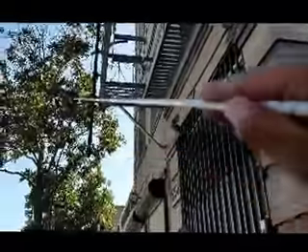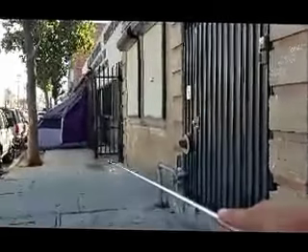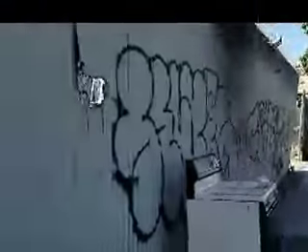Now this ladder, like I said, you're required to have this balance ladder drop 2 to 3 feet per second to the grade level. That way it'll allow occupants to evacuate and reach a safe haven, whether it's that area or this area. The whole point is for it to drop down, have occupants drop down, stay down at 2 to 3 feet per second, and allow for continuous evacuation from occupants who are in this building.